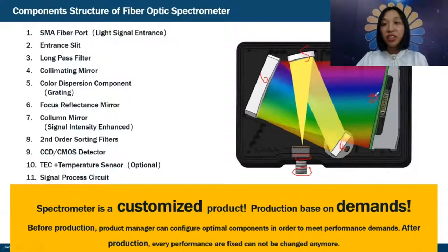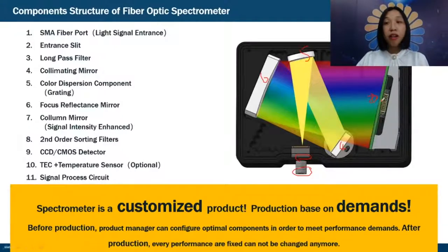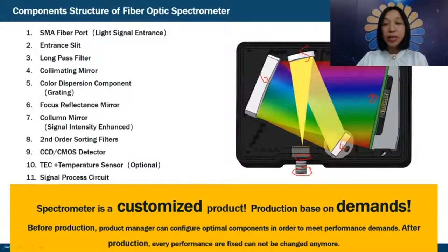If this spectrometer is cooled, you can also have a TEC cooler and temperature sensors. Component eleven — not shown in this picture because it's on the back — is the signal processor circuit board.